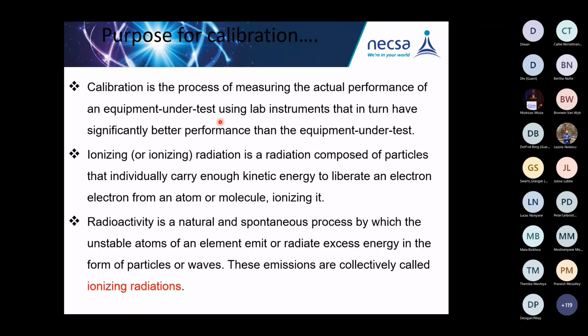Calibration is the process of measuring the actual performance of an equipment under test using a lab instrument that is intended to have significantly better performance than the equipment under test, the unit under test. The instrument that has significantly better performance is my reference standard, which is actually calibrated by NMISA. And then when I calibrate the client's or end user's instrument, I'm comparing that instrument with my instrument because it was calibrated by the NMI.